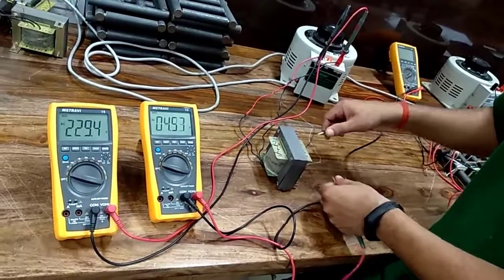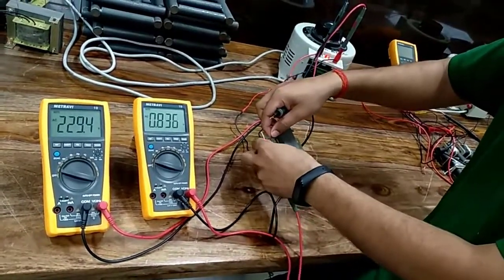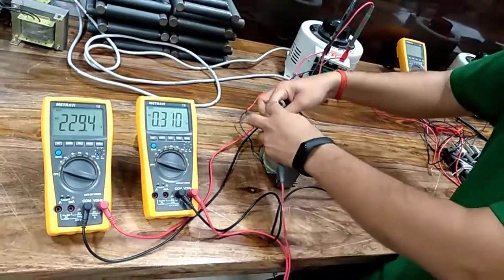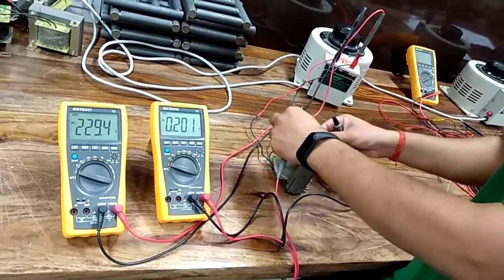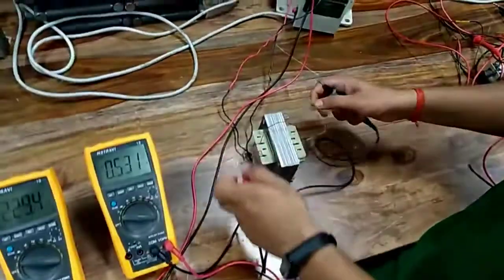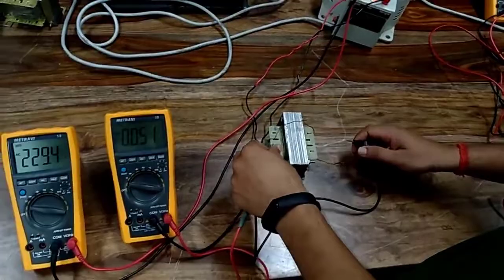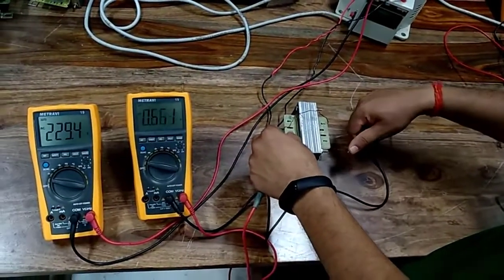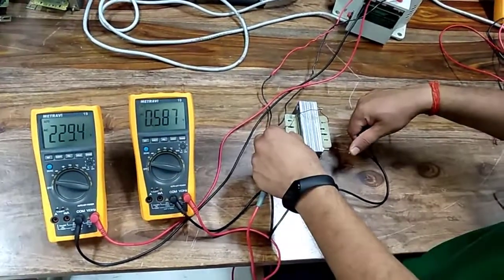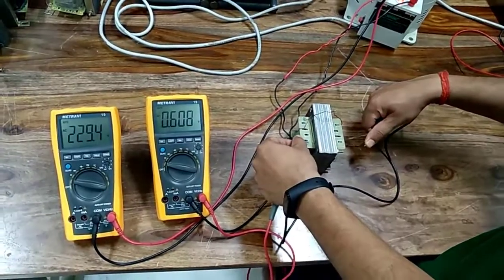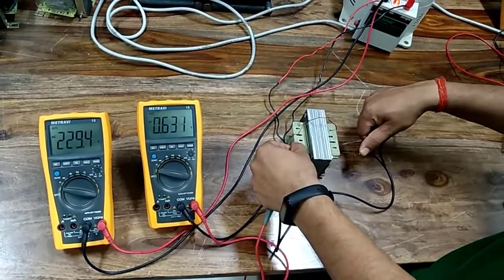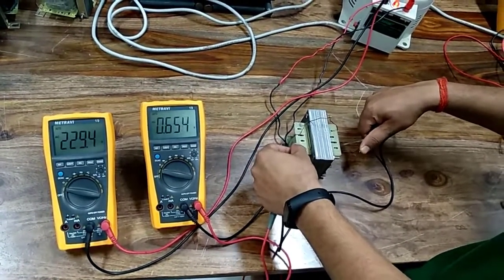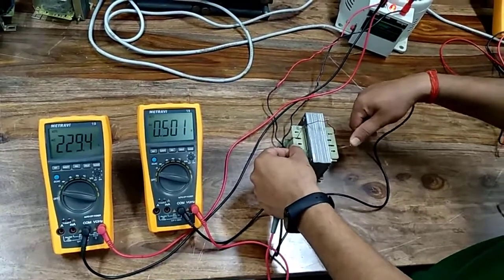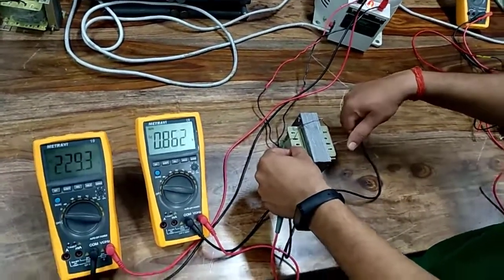The second thing we have to verify: we loosen this up and connect the other two windings of the transformer. Now we should get nearly 0 volts. As we can see, we are getting 0.57 volts. This means the fluxes are now in opposite directions and are cancelling each other out, so we are not able to get any voltage across the secondary terminal.